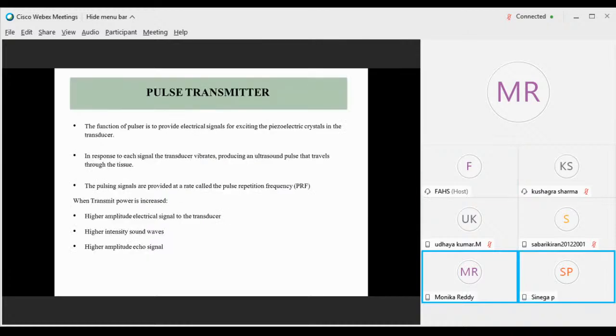So the pulse transmitter. The function of the pulser is to provide electrical signals for exciting piezoelectric crystals in the transducer. So the pulse signals will provide higher amplitude electrical signals and higher intensity sound waves, higher amplitude echo signals, which will eventually give a better image resolution. The rate at which the pulse signals are provided is known as pulse repetition frequency. At what rate we are repeating the pulse signals is known as pulse repetition frequency.